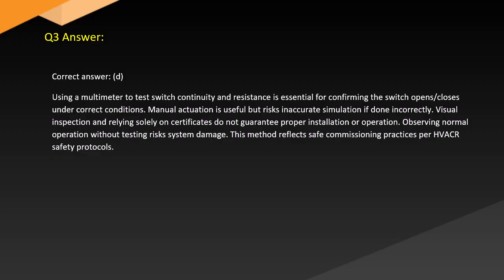Answer. Correct answer: D. Using a multimeter to test switch continuity and resistance is essential for confirming the switch opens and closes under correct conditions. Manual actuation is useful but risks inaccurate simulation if done incorrectly. Visual inspection and relying solely on certificates do not guarantee proper installation or operation. Observing normal operation without testing risks system damage. This method reflects safe commissioning practices per HVACR safety protocols.